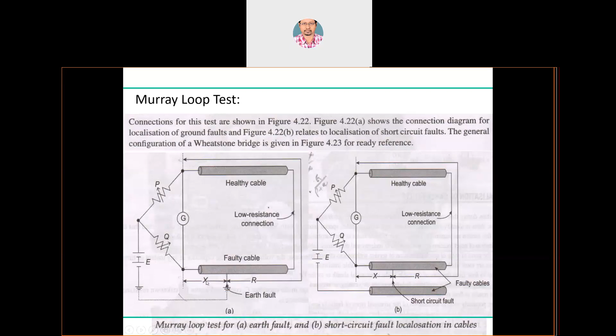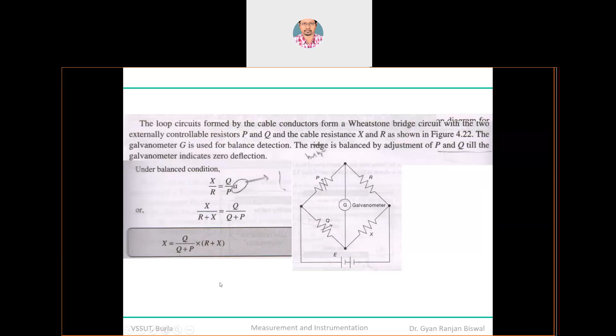Whenever you want to measure the fault location, this switch will be relocated from position B to A. So if you can do this rearrangement rather than the Murray loop test arrangement, you have to implement this in the ground. You cannot experimentally find out the location of the fault or the value of this unknown resistance, the distance Lx, in the field. It is a very cumbersome task.